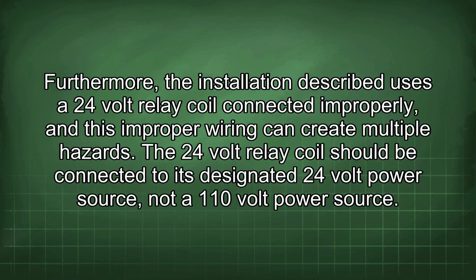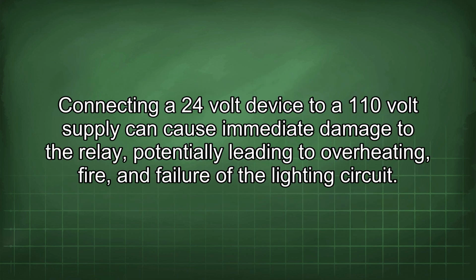Furthermore, the installation described uses a 24-volt relay coil connected improperly, and this improper wiring can create multiple hazards. The 24-volt relay coil should be connected to its designated 24-volt power source, not a 110-volt power source. Connecting a 24-volt device to a 110-volt supply can cause immediate damage to the relay, potentially leading to overheating, fire, and failure of the lighting circuit.